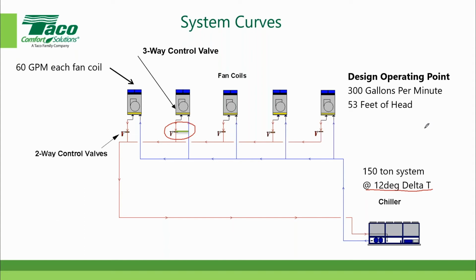Now, someone has to do a pressure drop calculation to find out how much pressure we need to get to the most remote point. In this case, we calculated it to be 53 feet. We're going to talk about that in a little bit more detail. Okay, so now we have the design operating point of 300 gallons per minute and 53 feet. Let's plot a system curve on a flow chart. Let's go over here, erase this, and go to the next slide.